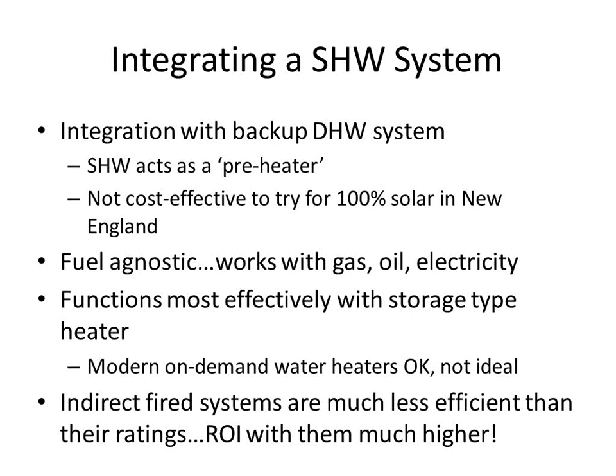The most efficient way to integrate a solar hot water system is to use some sort of storage-type heating system—a tank of water in the basement heated through another fuel source. That could be a conventional electric hot water heater with resistive elements, or an indirect fired tank where your boiler has a loop through it. Either way, you've got a mass of water being heated by another source.